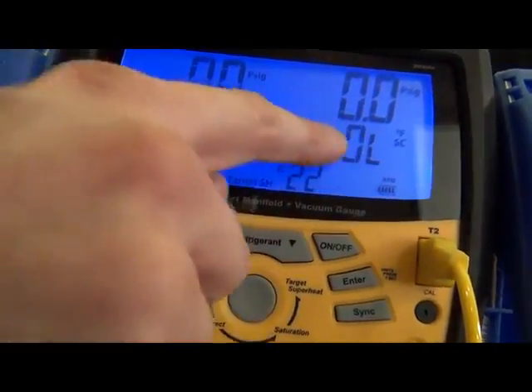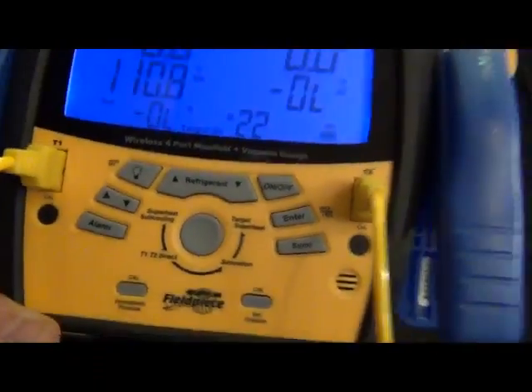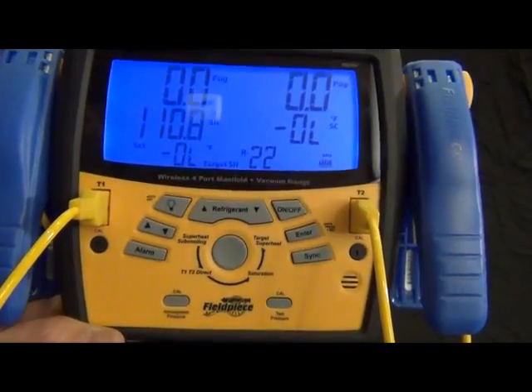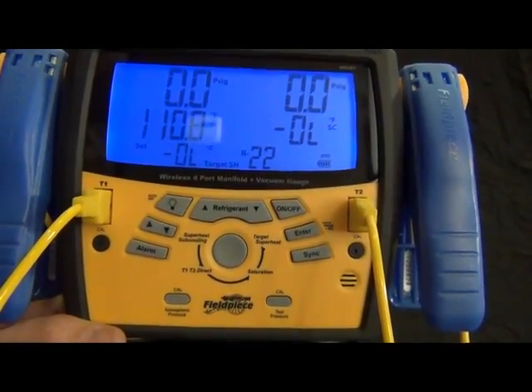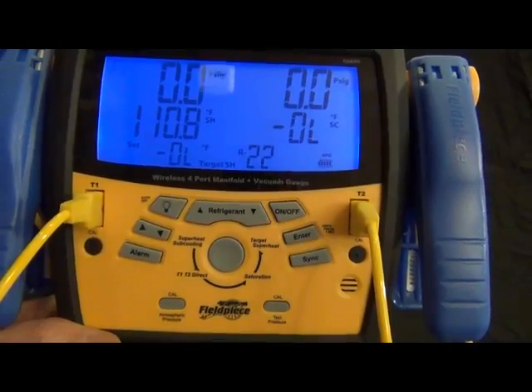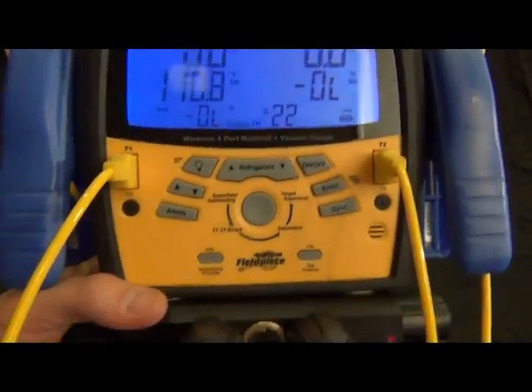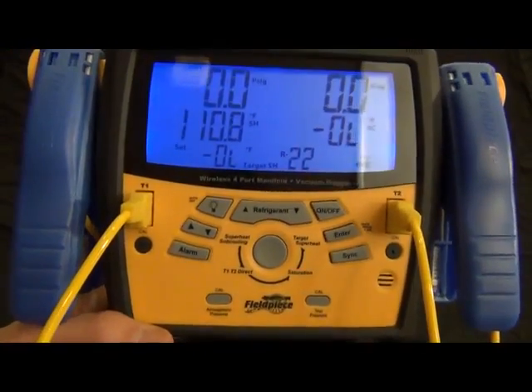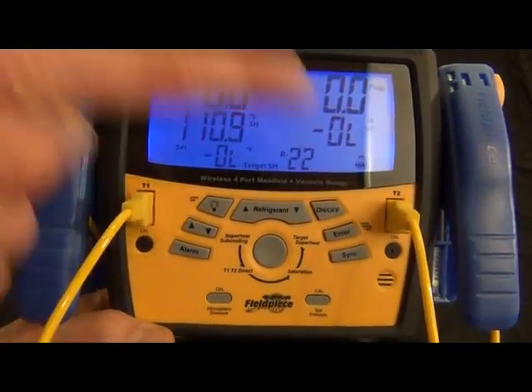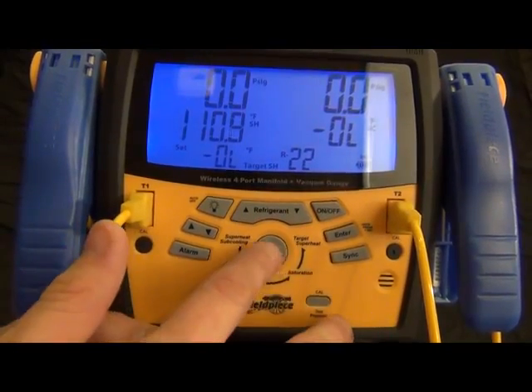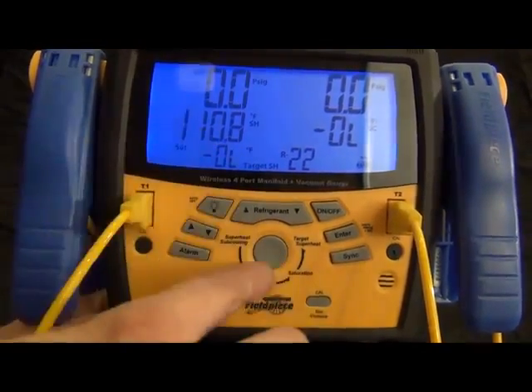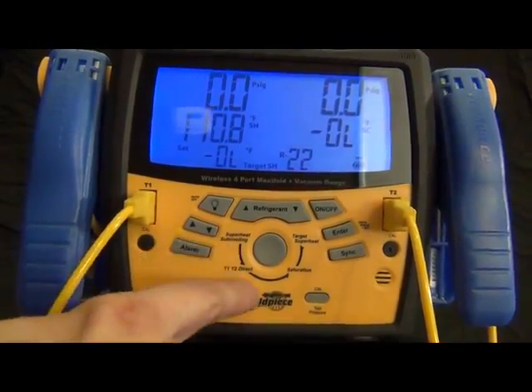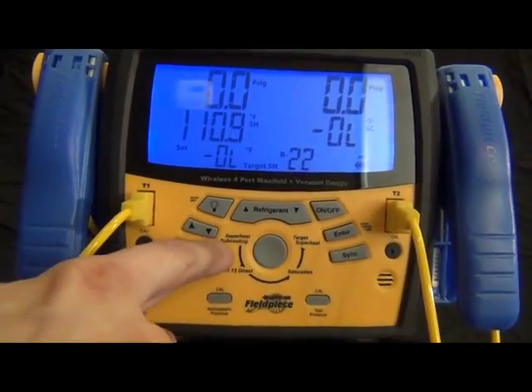There also will be a timer in this display right here that you can actually see how long it took. A lot of manufacturers will spec out that it needs to stay under, for example, a thousand microns for three or four minutes or whenever they spec out. And this way you can measure all of that. All right, next button is our mode button. This is probably one of the most common buttons you'll use. What it does is it cycles through these four modes.